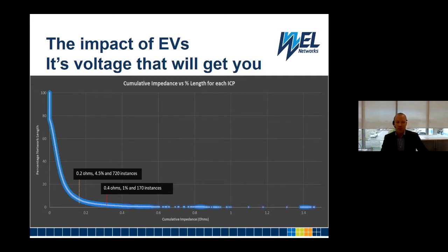A couple of important milestones here, and they're a bit rounded, but we have 170 instances where we get about 0.4 ohms, meaning a standard single phase EV charger will change my voltage by more than 5%. At 0.2, I'm looking at two EVs that will be able to do that, obviously on the same phase and similar location.